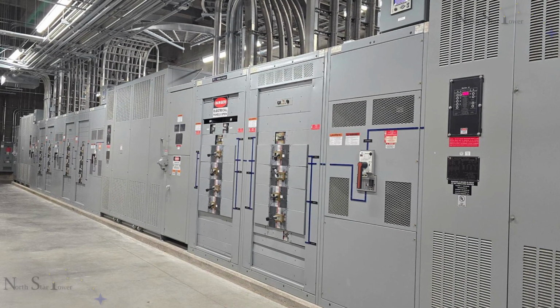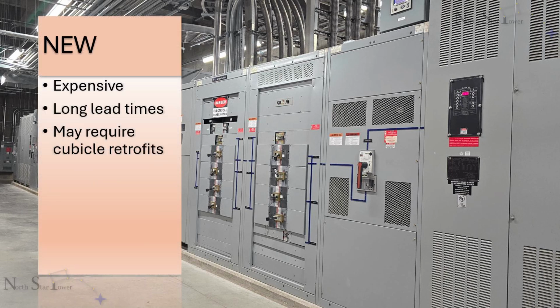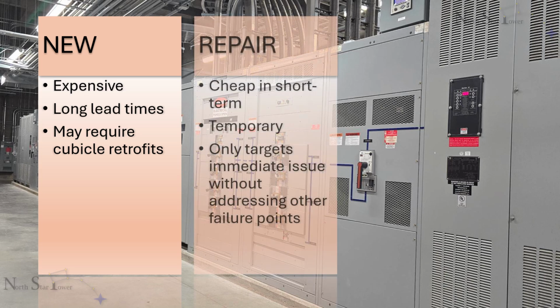When a breaker fails a test, action is needed. At that point, facility managers typically have three paths to choose from. The first is buying a new breaker. That might sound like the obvious solution, but in reality, it comes with a high cost, both financially and logistically. New breakers are expensive, often with long lead times, and in many facilities, the models they need are no longer manufactured.